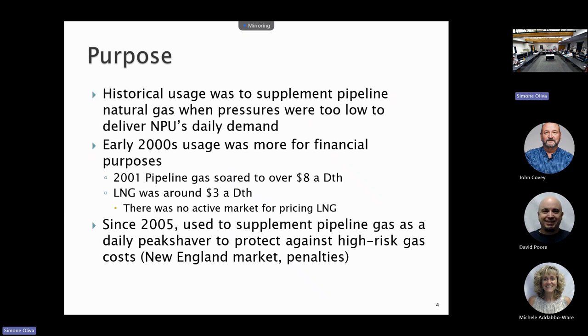Yeah, no, so we actually have 3, which we'll show you later. We have 3 modulating, cascading natural gas boilers in the control room, which are new in the last 2.5 years. And we actually heat a glycol mixture through a buffering tank, and that goes out to a vaporization coil out in the system. So we take the LNG and we run it through the multi-pass vaporizer, heat it up to a tolerable temperature to go out into the system in that 50-degree range. We then odorize it, and then it is put out into the system.